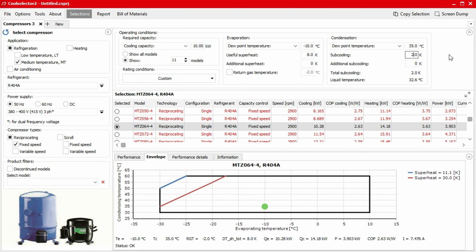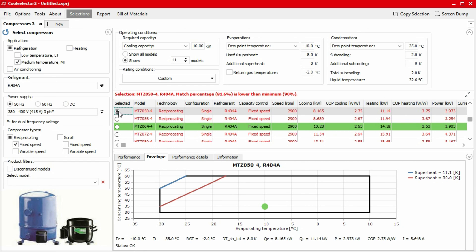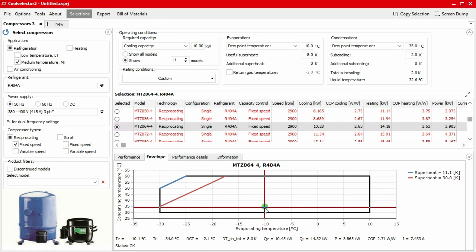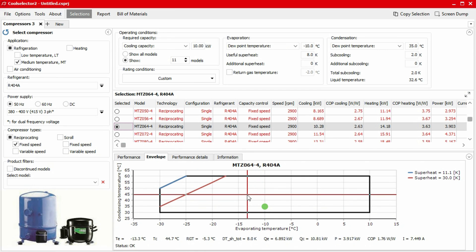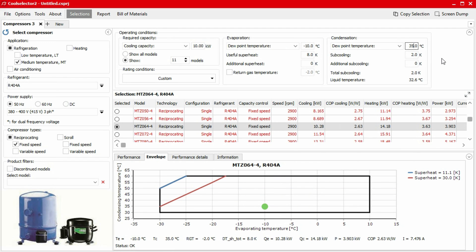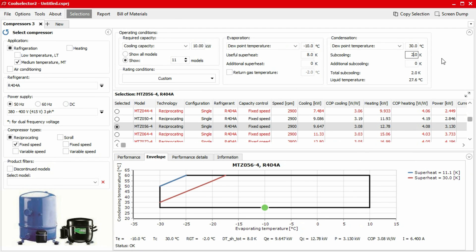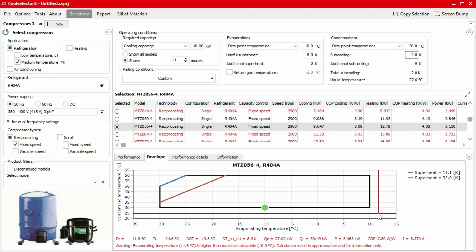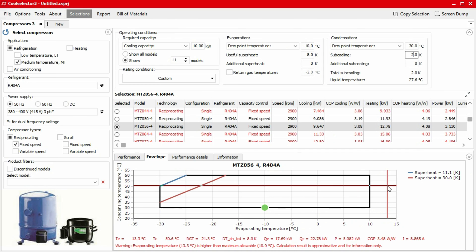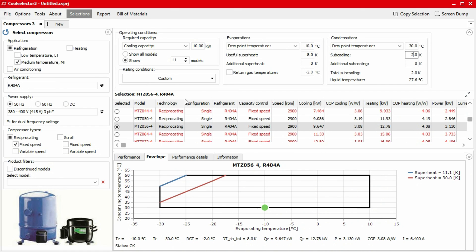The envelope represents the limitations of the compressor. Selecting a different compressor from the list automatically updates the performance graphs as well as the envelope. Underneath the envelope, we have a legend which provides valuable information such as temperatures, cooling capacity and power consumption. As we move our mouse on the screen, we can see the value changing, representing changes to the condensing and evaporating temperatures. If you choose a compressor and the green dot falls close to or onto the black line, the compressor may not run properly. If the compressor is operating outside of its design limitations, it could lead to compressor failure. A warning message will appear underneath the envelope explaining the issue with the operating conditions. If the green dot appears near, on or outside the limitations, then you should reconsider your selection.